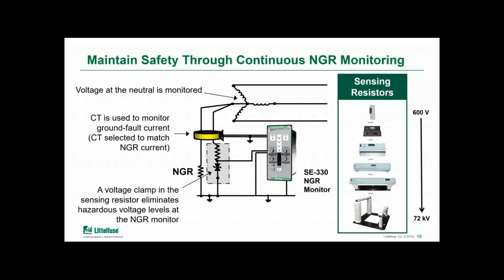And as is typical with these devices, there's a current transformer shown that measures the ground fault current as well. Once you have that package of measurements, the device can take that voltage, current, and resistance to not only verify the ground continuity, but also provide a backup. Even if there is an issue with the NGR and the system is ungrounded, the rise in neutral voltage and lack of current can be used to identify a simultaneous ground fault and resistor fault. So the package of measurements allows a very robust capability of monitoring the health of the system.